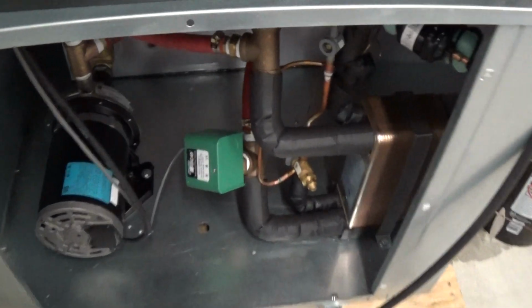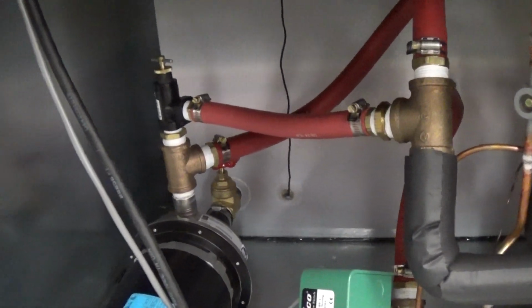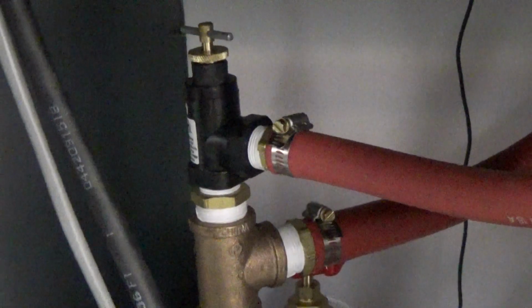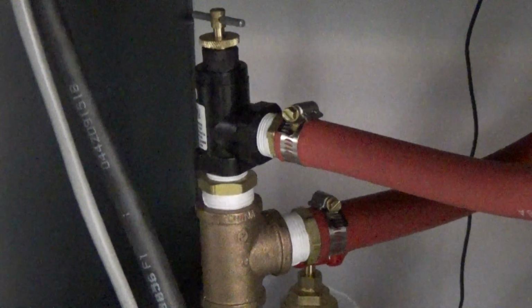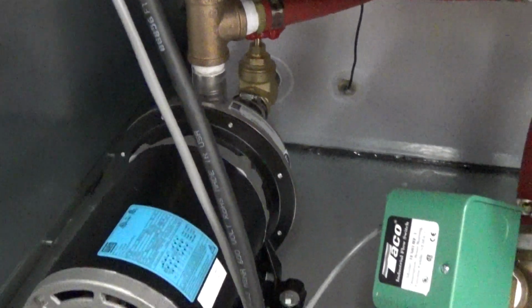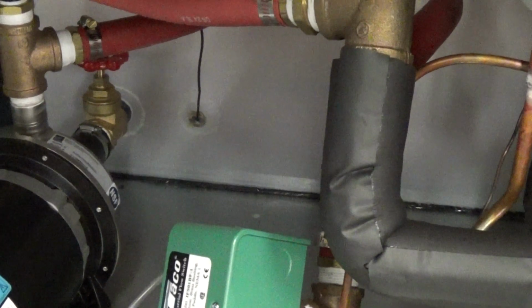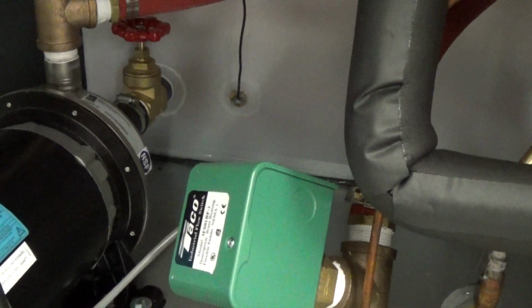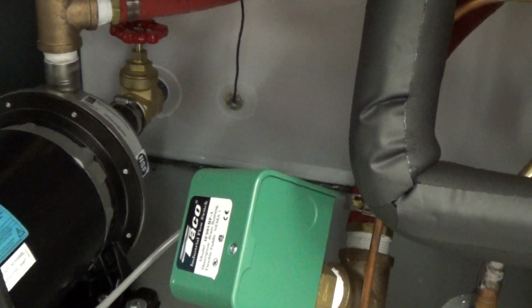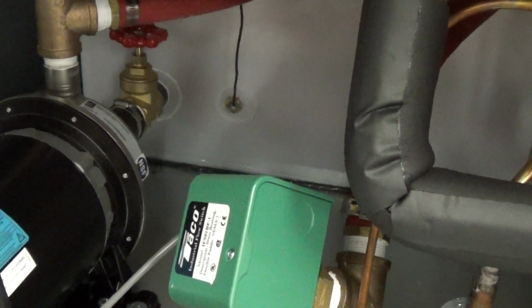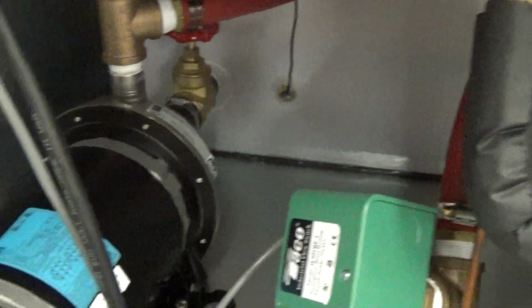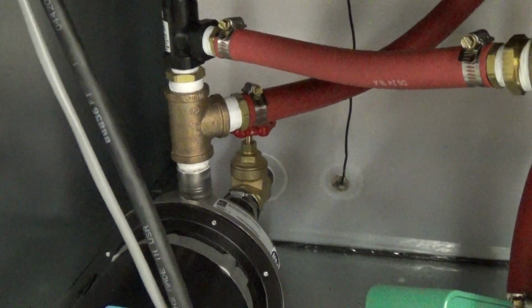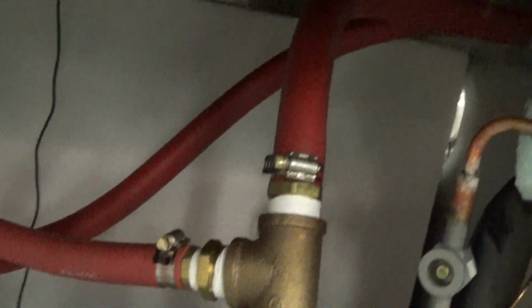One of the other things on the K-Chill here is we have this spring-loaded preset bypass, which is also set at the factory. So the pump draws from our storage tank, and that valve there you see with the red handle should remain wide open all the time unless you're powered down and servicing it. We draw from the tank. We come out and we go out. You see that line back there on the left. We go out to the process.